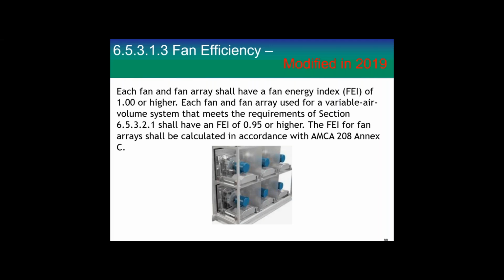But anyway, you should be able to get the FEI from every manufacturer in the fan tables. They'll give you the FEI and you just have to pick it. They'll warn you. Normally I see warnings now that say this didn't meet the FEI or something. FEI is a rating standard that was developed by AMCA, and they sold it to us and DOE.